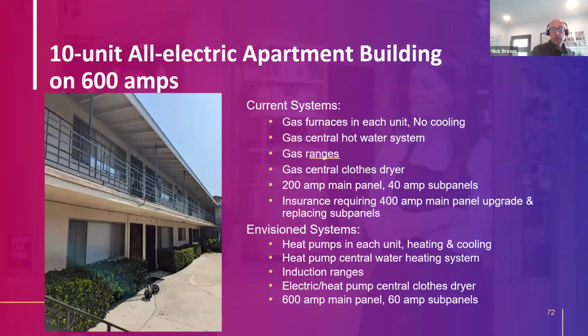Right now we're working with a multifamily example I wanted to share in our last minute. It's a gas heavy building: gas wall furnace in each unit, no cooling, central gas water heating, gas ranges, and a central gas clothes dryer. An attendee brought this up, it has a faulty panel, and the insurance company is refusing to continue covering the building until it's upgraded. They've determined 400 amps is the minimum size upgrade, and they also want to replace all the sub panels in each unit and the wiring in between. So we thought this was a perfect opportunity to electrify the building and use incentive programs to pay part of the cost of what they're being forced to do anyway.